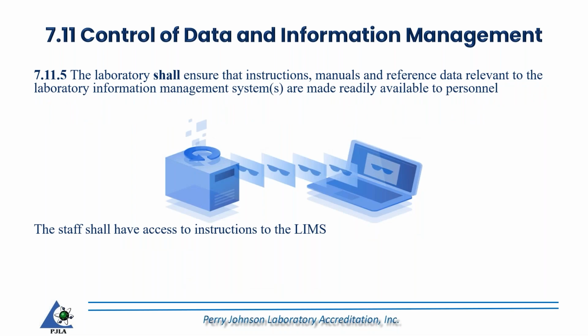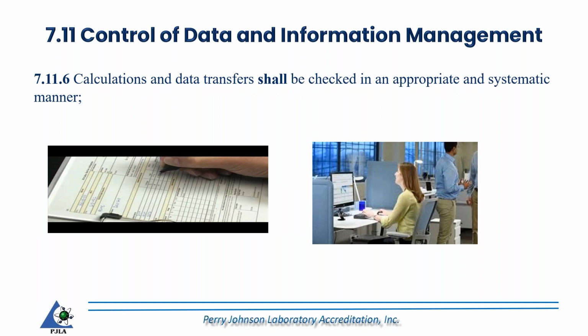The laboratory shall ensure that instruction manuals and reference data relevant to the laboratory information management system are made readily available to personnel. In other words, if you have a laboratory LIMS, laboratory information management system, staff should have access to those instructions. Calculations and data transfer shall be checked in an appropriate and systematic manner. So perhaps you're going from paper copy to electronic copy. I often see this with those folks that are doing on-site calibration. Some folks don't allow computers to be brought into their facilities, and data could be handwritten. So this is when you're going from handwritten to electronic. That needs to be checked in a systematic manner as it goes through that transfer.